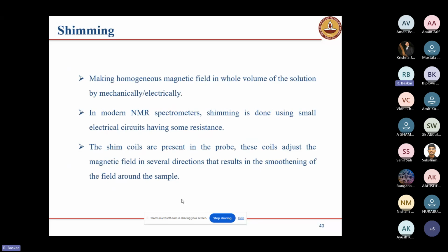In that case, if we are not doing the shimming, the top portion will give one signal and the bottom portion will give another signal. These are very close, so finally we will get shoulder-like signals. We want to avoid these things. That's why we are doing shimming. Shimming makes the magnetic field homogeneous in the whole volume of your solution. In the top portion, whatever molecules are there feel the same effective magnetic field, and the bottom portion also feels the same effective magnetic field. It will adjust both. Then finally we will get a sharper signal.